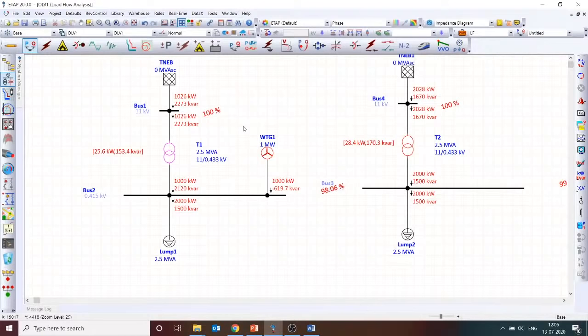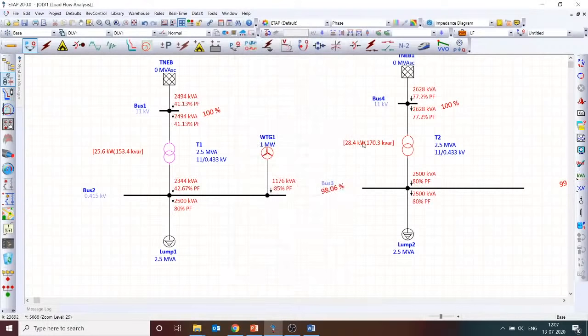Okay. Now, the other factor, is it the only factor? Answer is no. Here, even without a wind turbine generator, I have not maintained the power factor at 0.9. For that, I will receive a penalty for the power factor. That is one thing. But after adding a wind turbine generator type 1, what's the problem which I have faced? That's what I am explaining here. The power factor has reduced further from 0.7 to 0.44. And if you look at this, you will be put under a huge penalty for that.